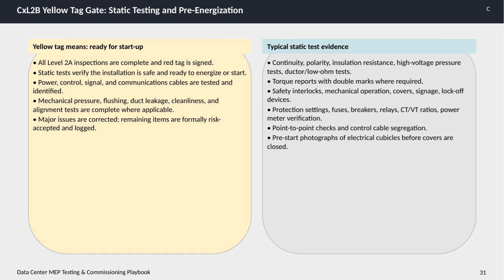Protection settings such as fuses, breakers, relays, and CT/VT ratios are validated, along with power meter checks. Control cables undergo point-to-point inspections and segregation checks. Finally, pre-start photographs of electrical cubicles are taken before covers are closed, providing visual proof of the system's condition at this critical stage. This thorough process ensures the system is fully prepared and safe for the next phase of commissioning.